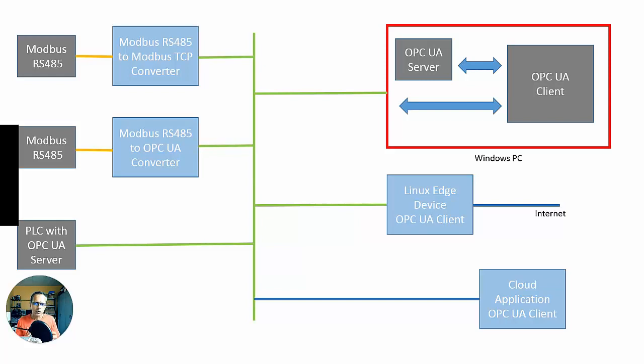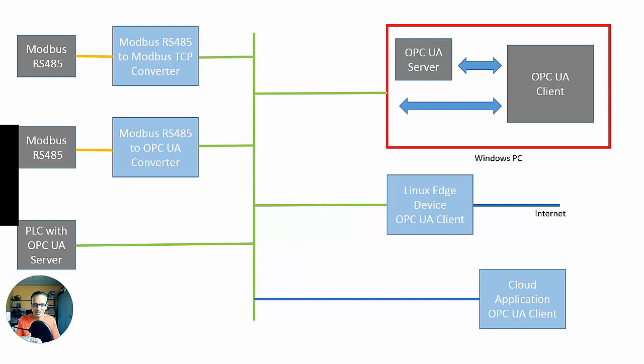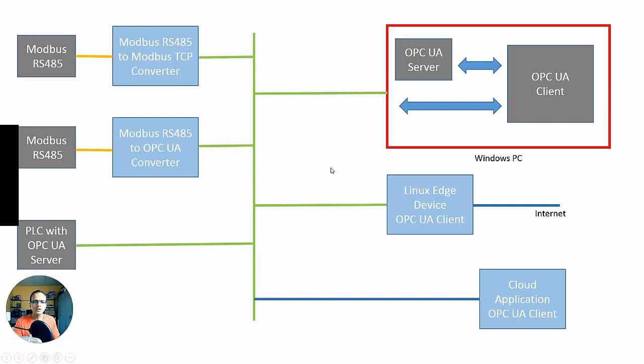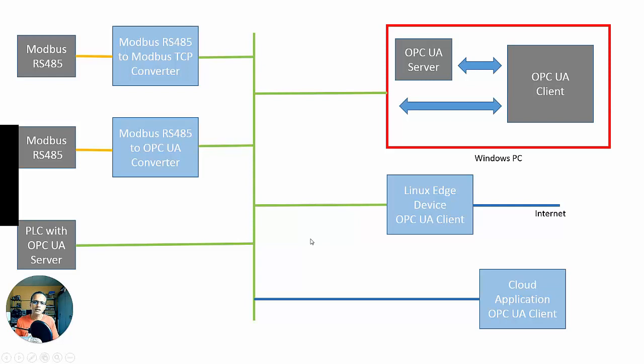Okay, so now point to note, protocols like Profinet, Profibus, Modbus TCP, Ethernet IP, and whatnot, on the plant floor itself, OPC UA is not going to replace those. It's not meant to. Those protocols that I mentioned offer a certain degree of network determinism that you need on the plant floor. OPC UA is not going to come in there. OPC UA is going to come into the space here of connecting enterprise applications to your plant network safely. That's the potential of it.